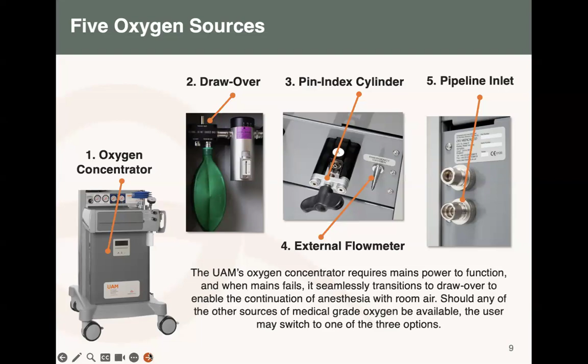The last option is for emergency. In the event you have a patient and the source of oxygen is not supplying enough, that's where you use the emergency one. Remember, when you connect the emergency oxygen, the machine will provide an alarm indicating that you have an emergency. So the UAM has five sources of oxygen, and all of these can be used when using the machine. But the main one should be your concentrator. But in the event that the power has gone off and you cannot use the concentrator, that's why we advise you to go with the other sources. Next.